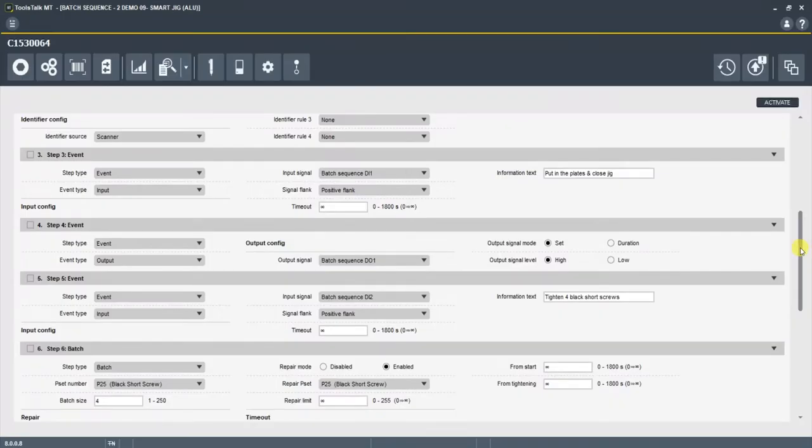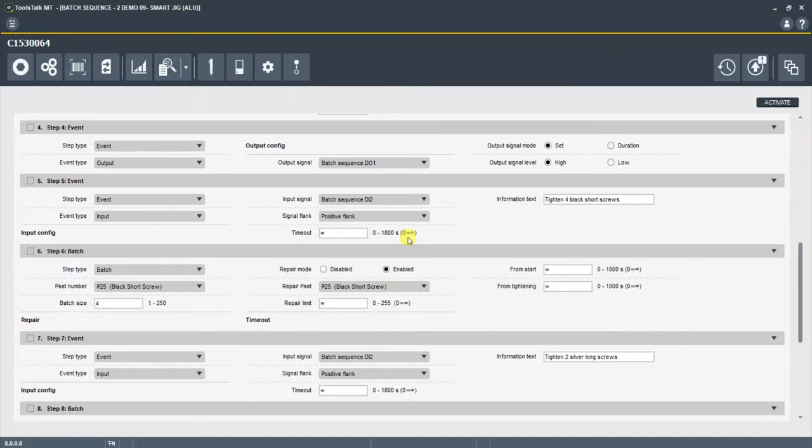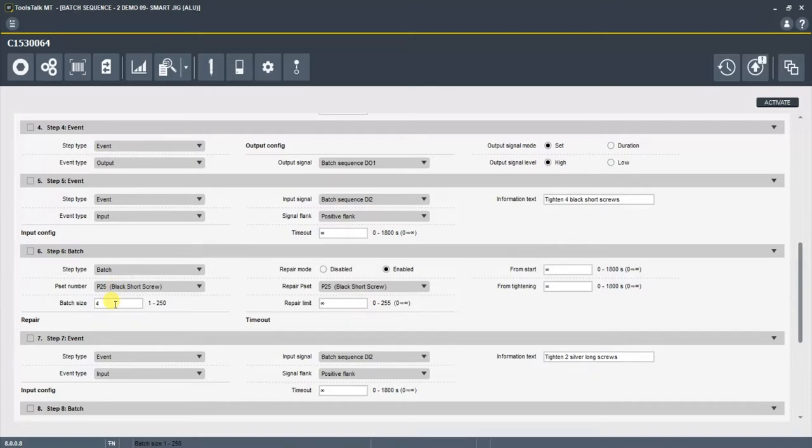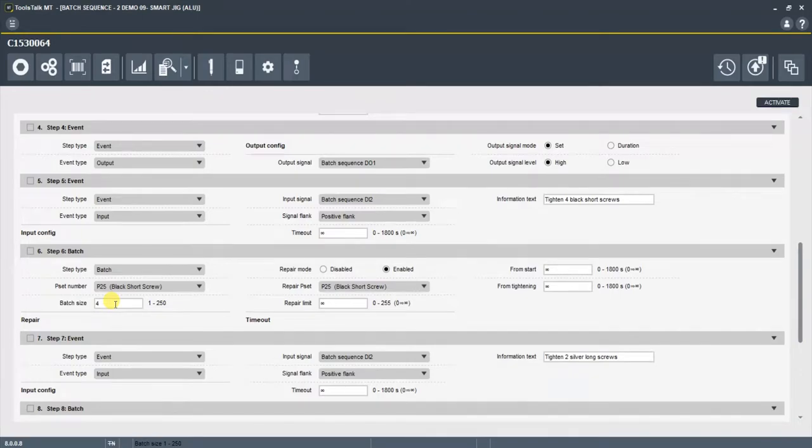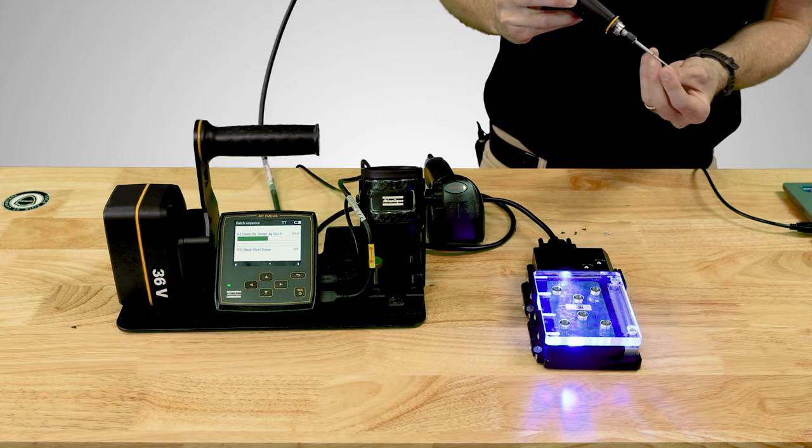The next step is the basic batch step that we talked about at the beginning of the video. So in a batch, now we know that we're going to tighten those four black short screws. And we want to use P set number 25, which is a tightening program that we made specifically for these short black screws. The configuration is going to look for four okay results before it moves into the next step in the batch configuration. So I've got four short black screws here.